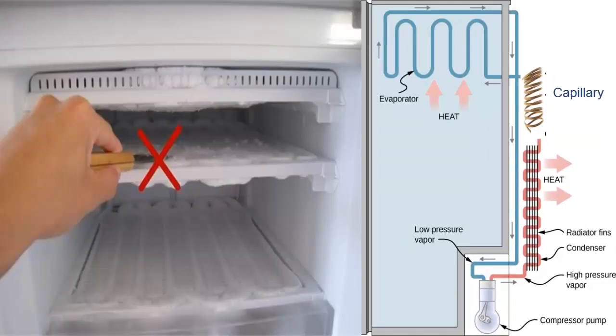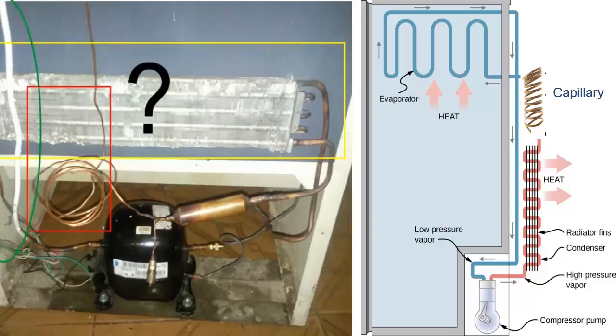Step 9. Visually check for the absence of oil marks, likely indicating a leak. Additionally, remember that an unobstructed capillary tube, working correctly, should not exhibit external freezing.